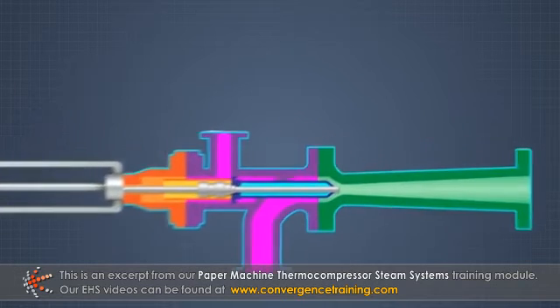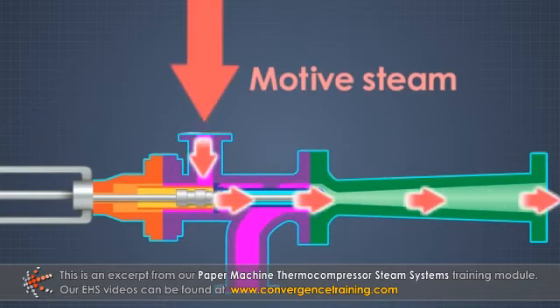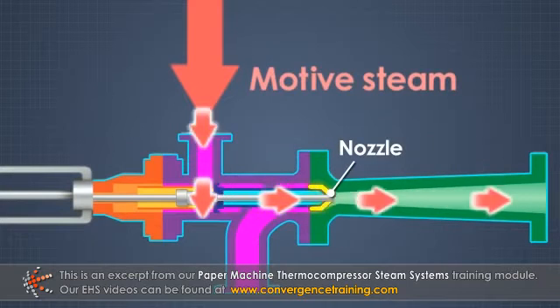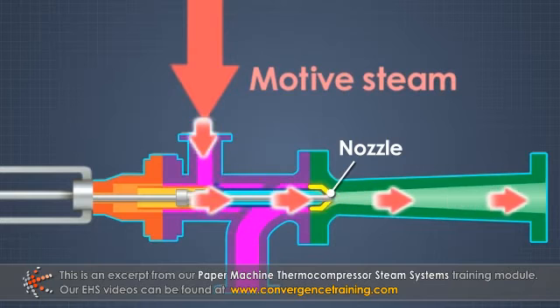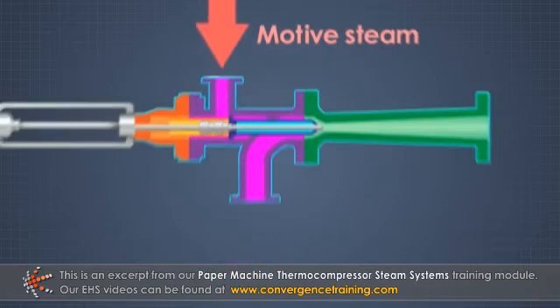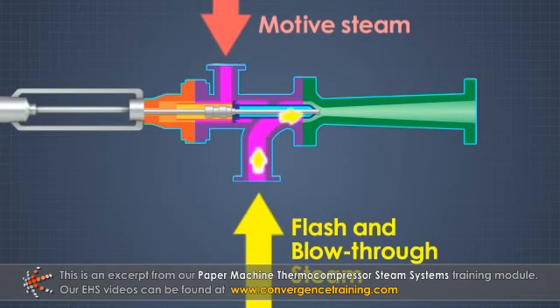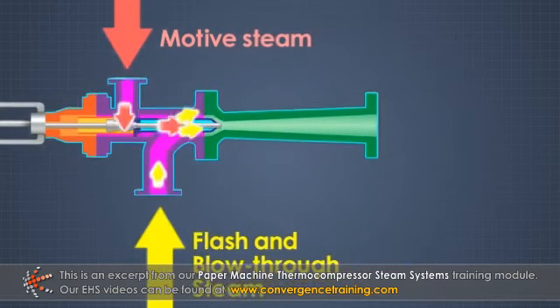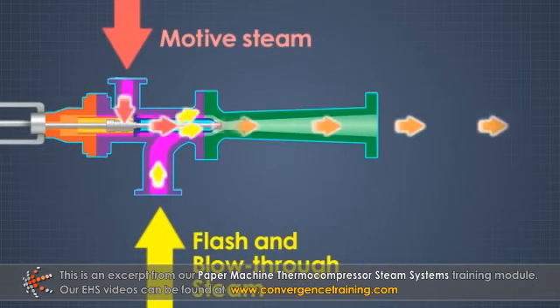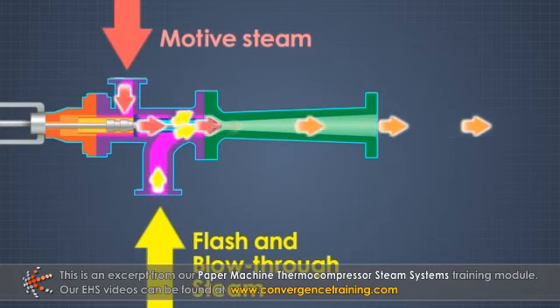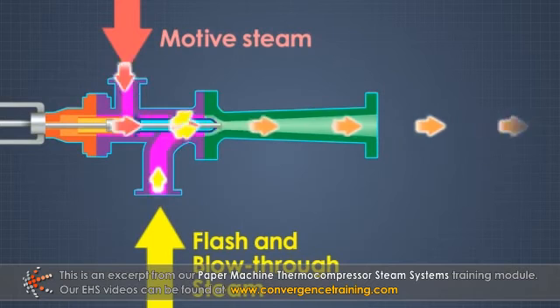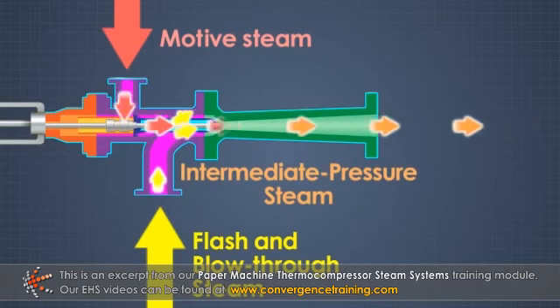In a thermocompressor, the high-pressure motive steam passes through the nozzle, which significantly increases its velocity and lowers the pressure at that point in the device. Steam from the condensate separator tank is pulled into this low-pressure area. As the combined steam moves through the diffuser, the velocity decreases and the two steams come to thermodynamic equilibrium, and an intermediate pressure steam emerges.